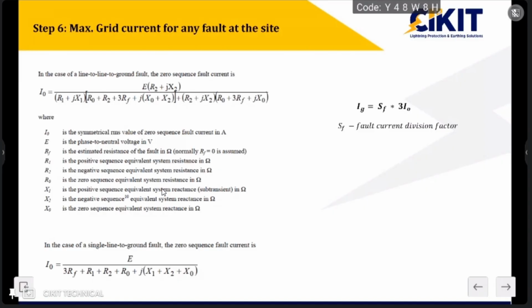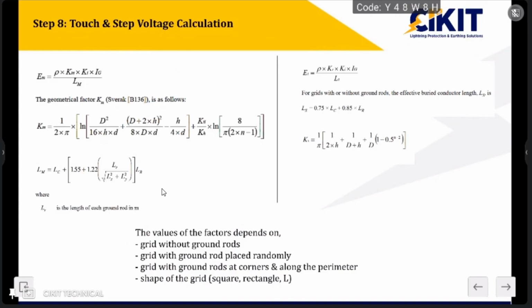When we have a number of transmission networks in a particular area, the current will have multiple parallel paths. If the number of parallel paths is higher, then the portion of current that returns to the source through the soil will get reduced. So if I am working with a substation which has a lot of feeders, then the Sf value will be different, and based upon the Sf value, the grid current value will get reduced. In general, we consider the Sf value as 50% to 60%, but there are certain conditions where the Sf value was even lesser than 0.3. So it depends upon each and every site condition. We don't have any general rule for deciding what the Sf value will be.